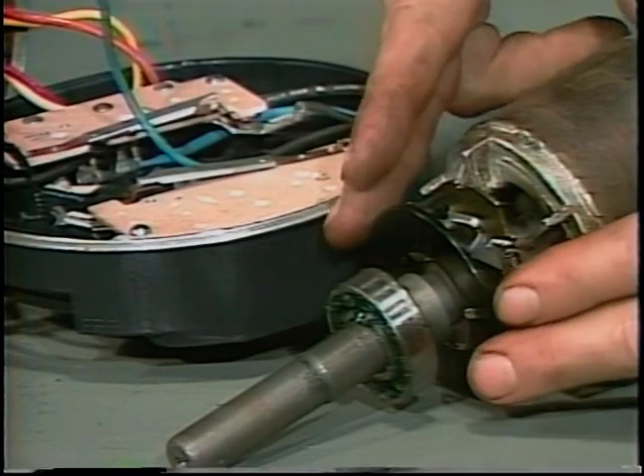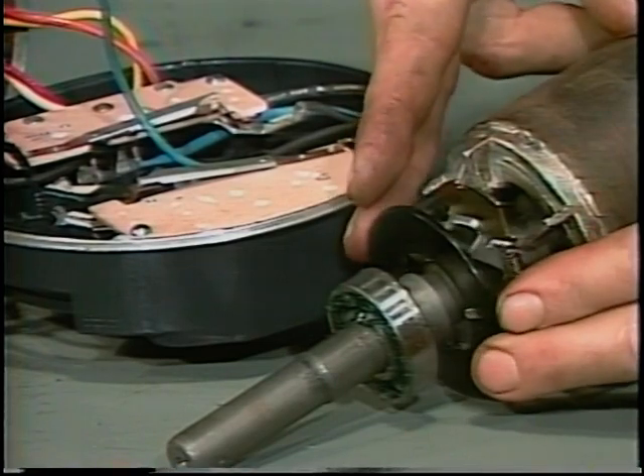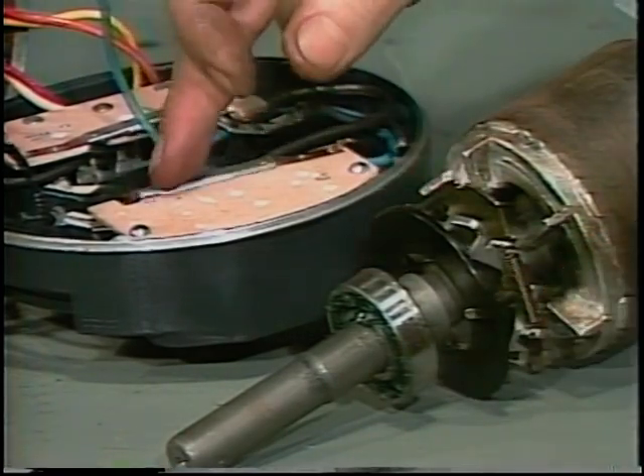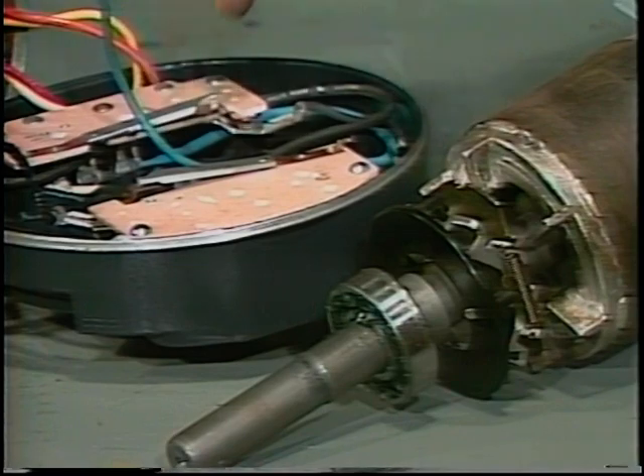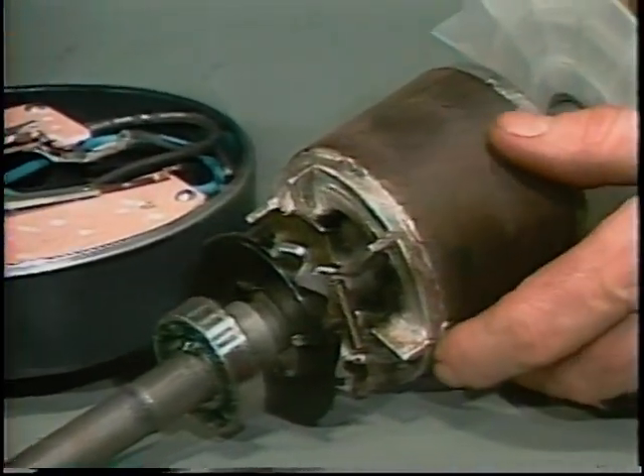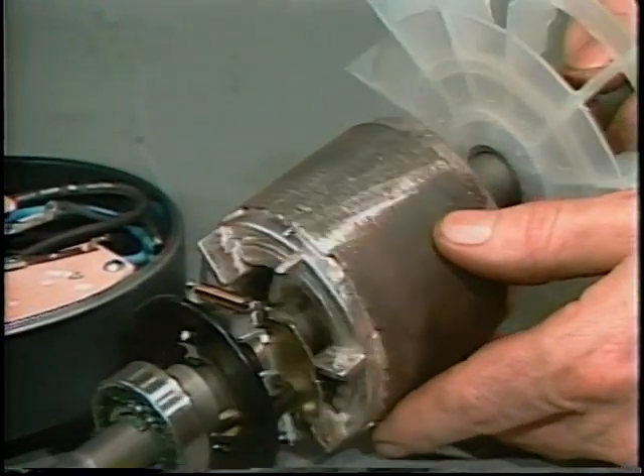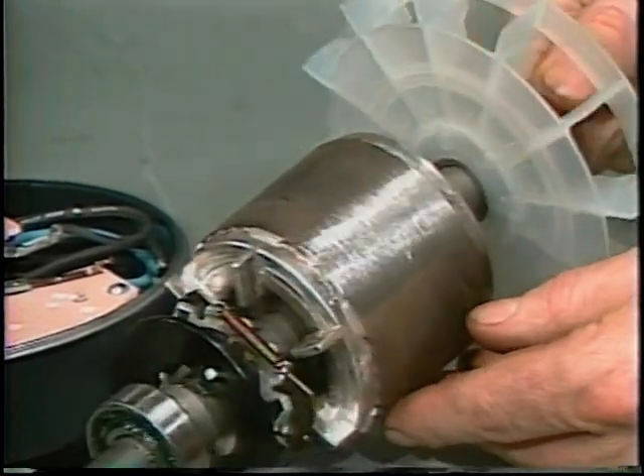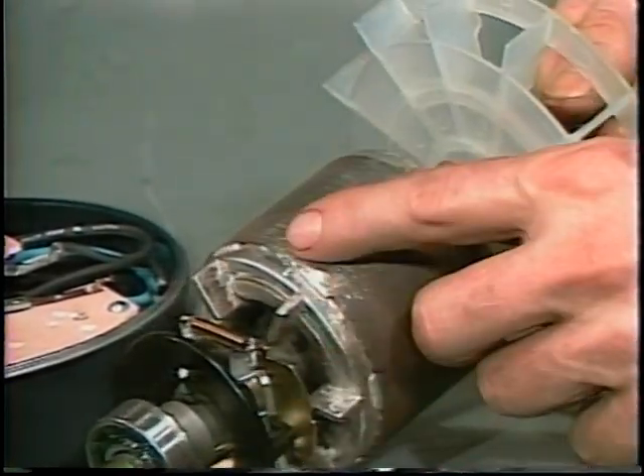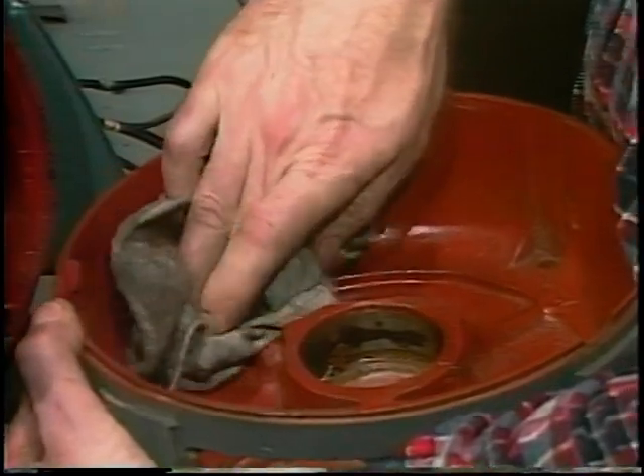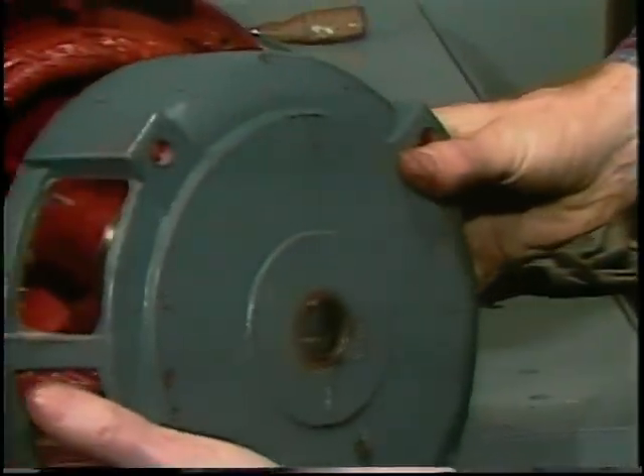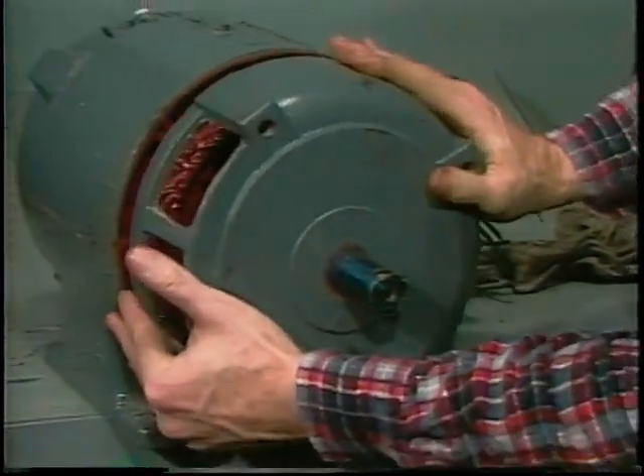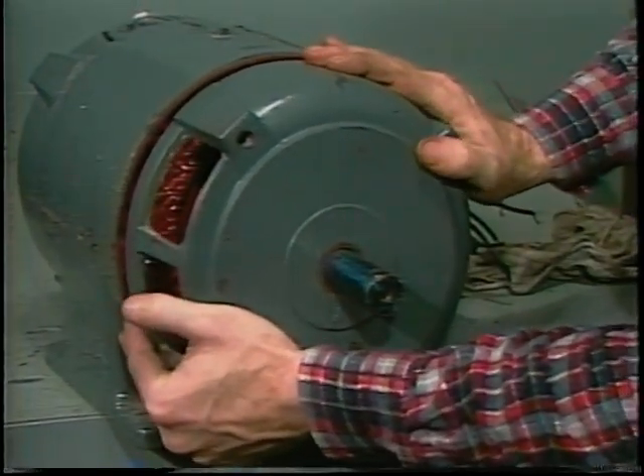If a motor has a centrifugal switch, check the parts for wear and the contacts for excessive burning or pitting. Fresh grooves or shiny spots on the rotor and stator probably indicate rubbing due to a bent shaft or loose bearings. Clean out the motor thoroughly before you put it back together. And as you reassemble it, check for loose bearings or a rough feel in the bearings.